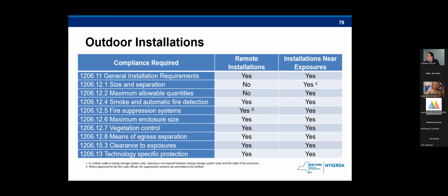We would always recommend some sort of battery suppression system to be available to control a potential fire inside of walk-in containers when the fire department responders cannot get water inside the container. But regardless of the fire department's well-intentioned efforts to extinguish the fire, fire departments can take a defensive posture in this case and not allow the fire to spread to other containers, and basically just contain it if there is a fire.